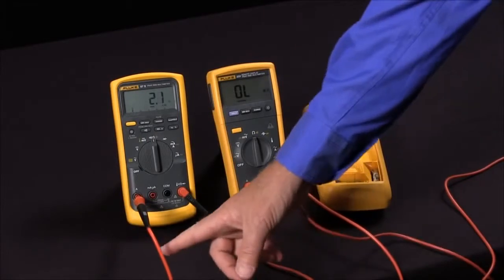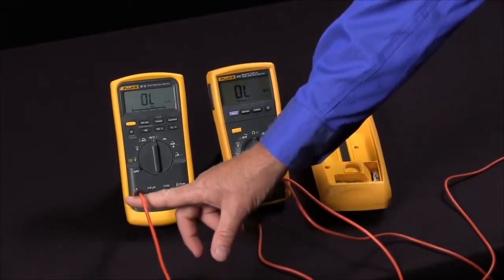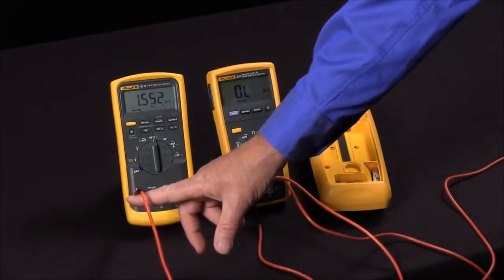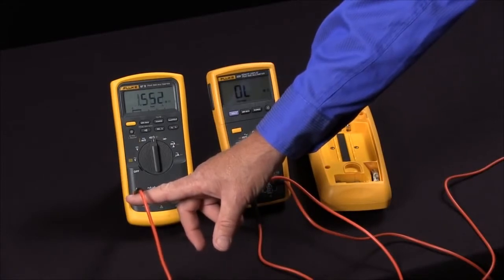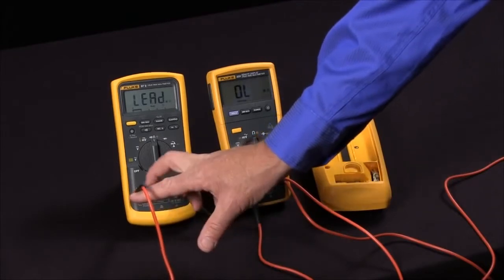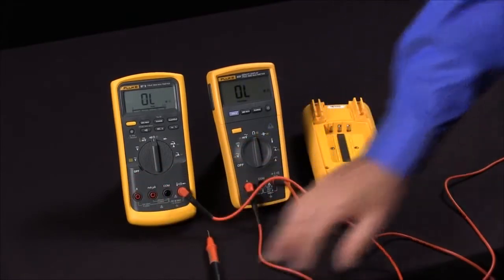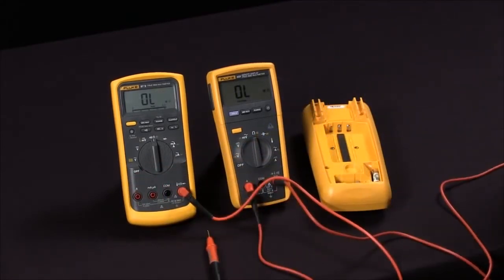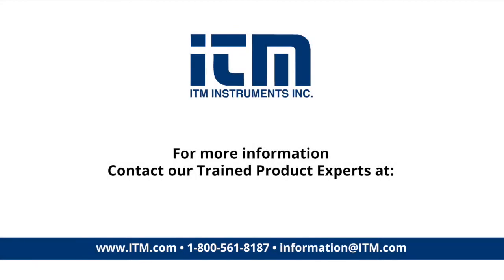One thing nice about the Fluke 87 is they have this lead alert function, so if you're trying to take a measurement with the leads in the wrong jack, it will actually give you an indication. This is also an indication that your fuses are okay. So this is a way that you can test the fuses within your multimeter without having to open the case.